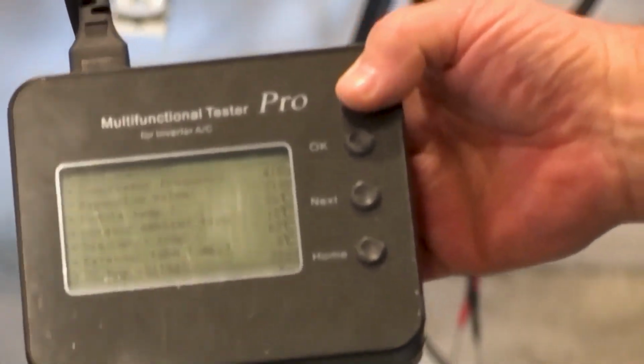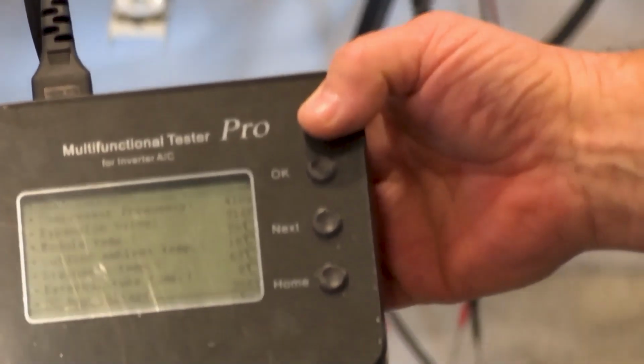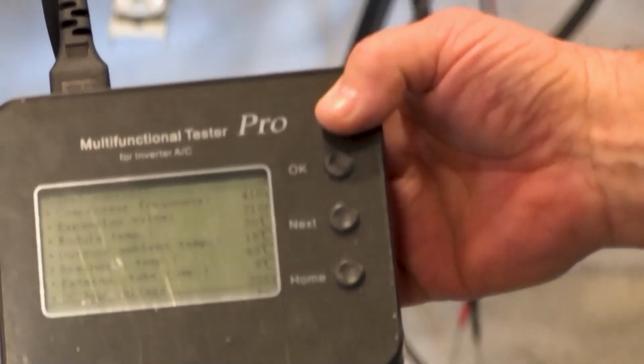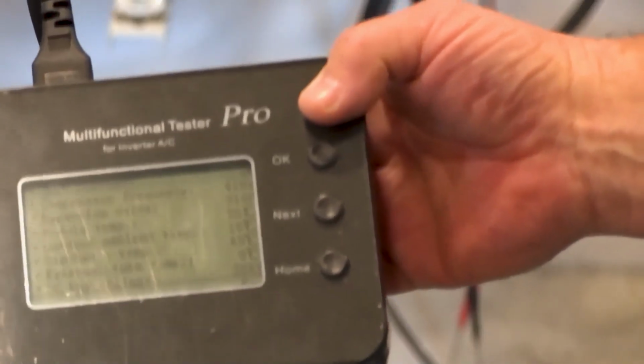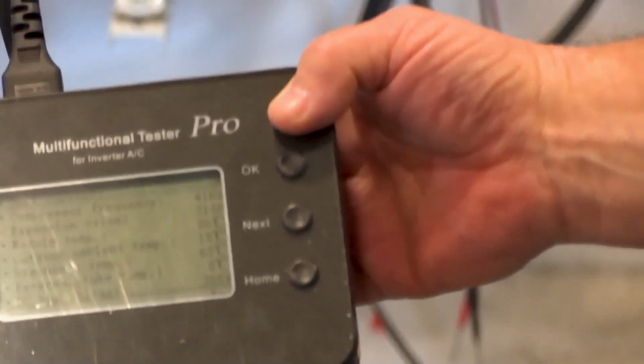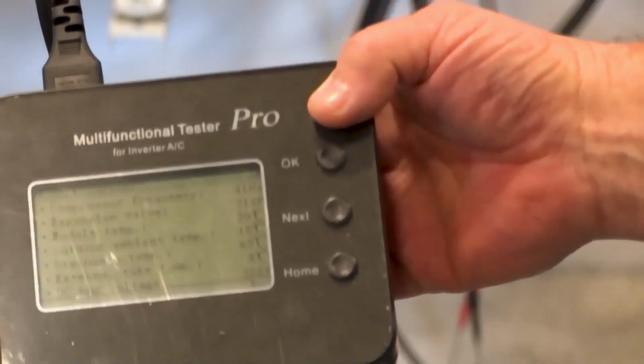So then you take that same machine, the leak gets repaired or whatever, you evacuate it, you weigh the charge back into it. Now you sit there and monitor that discharge temperature, and as you're bringing on those indoor units, that discharge temperature doesn't keep creeping up like that. And you start getting into a more normal zone. I can't just blatantly tell you, hey, this is the discharge temperature you should be running at, because your load conditions change all that, right? But 150 degrees, in my experience, is not an excessively hot discharge temperature, okay? But when I start getting 175 plus, now I'm starting to get concerned.